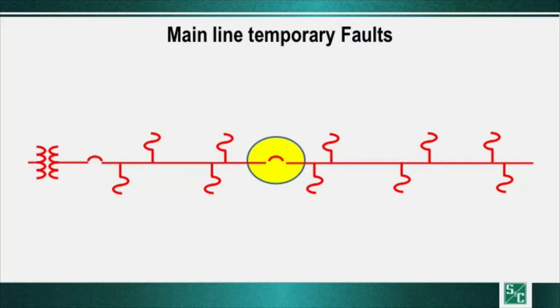How this helps: if you have a fault on the far side, the second half of the feeder, that device in the middle of the circuit interrupts the fault, and the people on the first half of the feeder don't see it. So it reduces momentaries and sustained outages in that way.